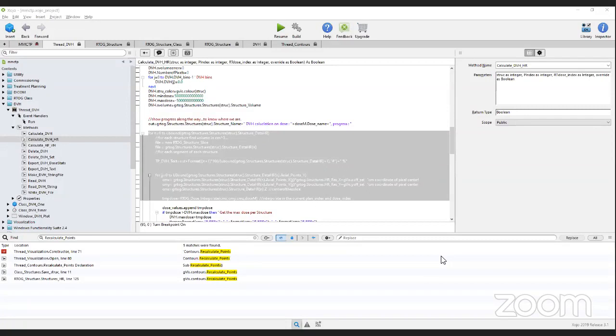And then the DVH calculation that I've just described, you'll be summing up all of those integer points within the structure and assigning a delta volume to each integer, and you multiply it by the number of integers, and that's your structure volume.